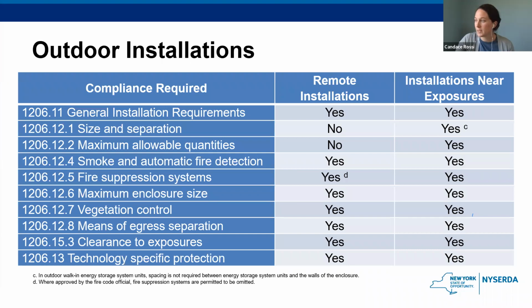So here, once again, we have another chart showing the requirements for outdoor installations. Remote systems may not have the same requirements as outdoor installations near exposures. These remote systems do not have the same life safety risk factor involved, so their requirements are less stringent. You can see this specifically when it comes to the fire suppression systems. It has a fun little asterisk. Where approved by the fire code official, fire suppression systems are permitted to be omitted.